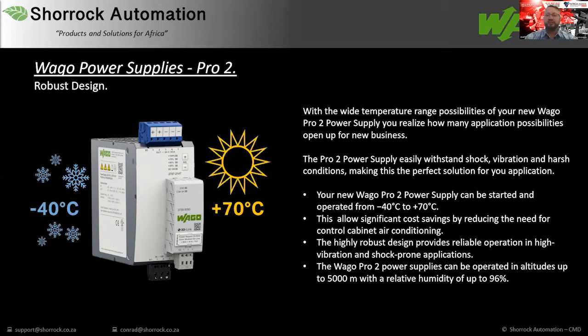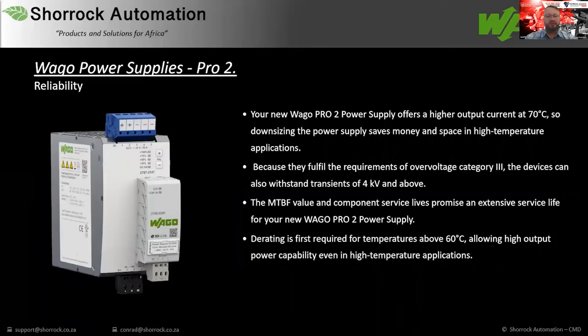This allows for significant cost saving by reducing the need for control cabinet air conditioning, as I mentioned. In addition, the highly robust design provides reliable operation in high vibration and shock-prone applications. The WAGO Pro 2 power supply series can be operated at altitudes of up to 5,000 meters with a relative humidity of up to 96%. Okay. In terms of reliability, I'd like to carry on. Your new WAGO Pro 2 power supply also offers a higher output current at 70 degrees Celsius. So downsizing the power supply saves money and space in high temperature applications.